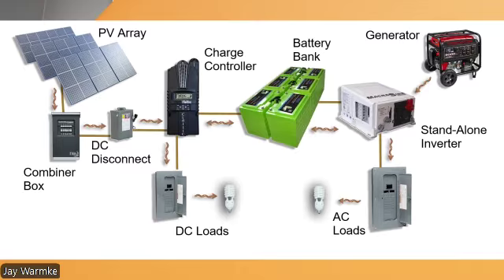And then there's typically, and this is the old lead acid battery systems, where you have a charge controller. The charge controller is just a traffic cop between the array and the battery bank. It says, okay, let's not overcharge our batteries - we're going to pull power from the array and put it into the batteries. If we don't need any power, we're going to stop power from flowing. We're also going to prevent battery power from flowing up to the array when it's dark, because the array can actually serve as a load, so there's a blocking diode in there.